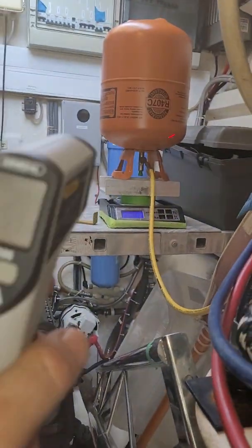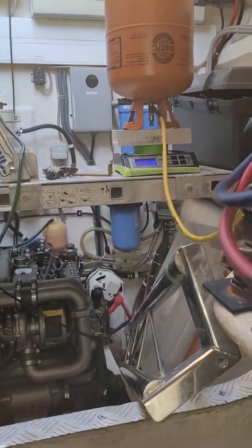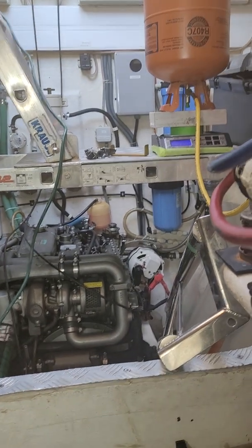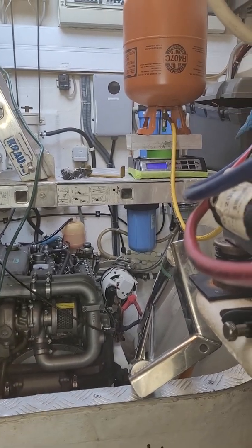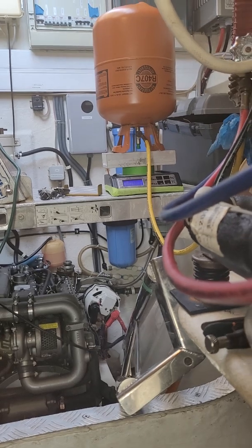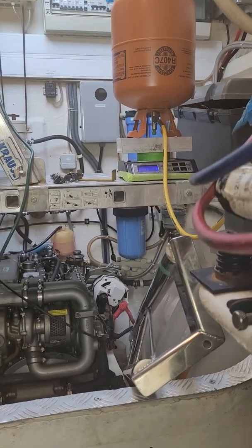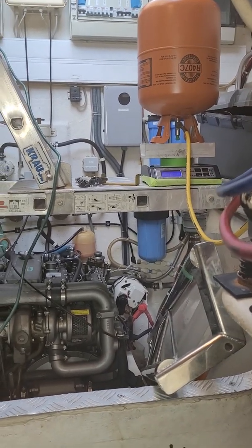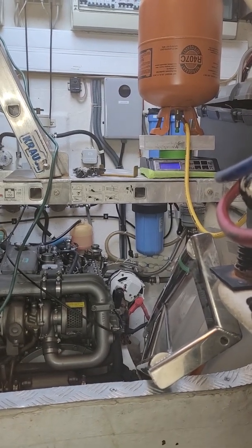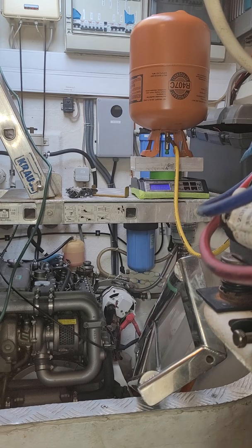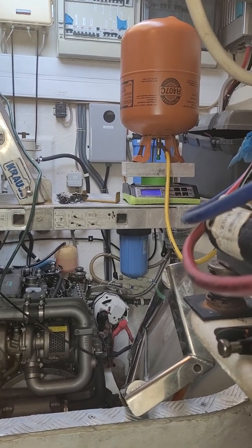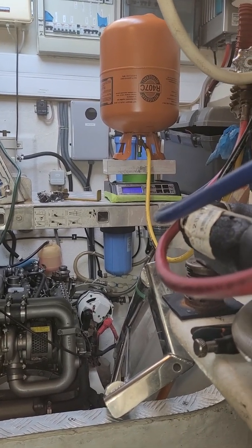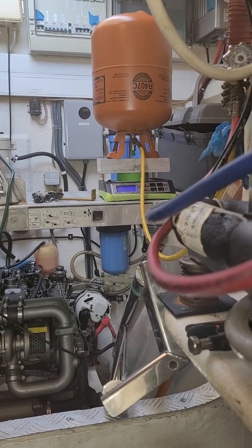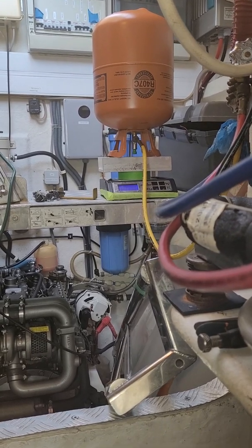The other thing important, when you charge gas, this gas is a mix of different gases. It's a blend of different gases. And the reason it is a blend is they put different molecules in there, like pentafluoroethane, bigger molecules to carry more thermal energy. And what happens is when you fill the system, when you fill a lot of gas in, if you have the bottle standing the right side up, one of the two molecules might boil off faster than the other.